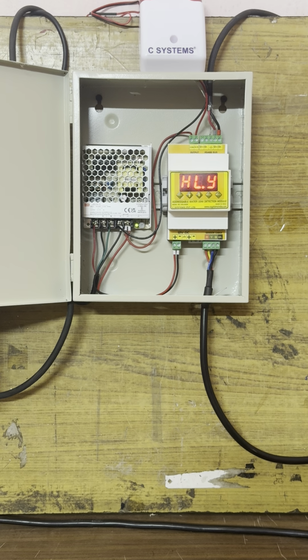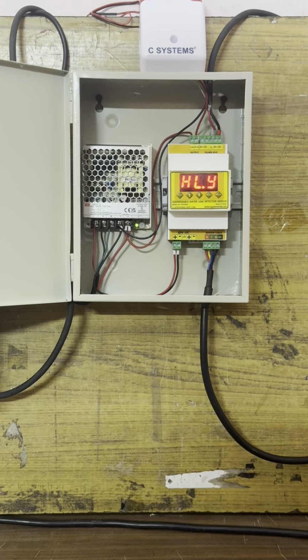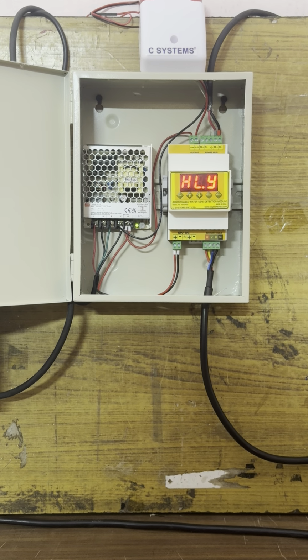The other limitation is during the addressing, the module should be addressed in such a way that it should start from 0.1 and there should not be any missing of IDs in between the SIMs. Suppose we cannot keep a configuration like 0.1, 0.2, 0.3, leaving 0.4, the next module cannot be 0.5. So it should be a continuous numbering. From first ID to the consecutive ID, the ID should be kept as 0.1, 0.2, 0.3. We cannot miss an ID in between the two IDs. This will lead to indication of fault in the master panel.